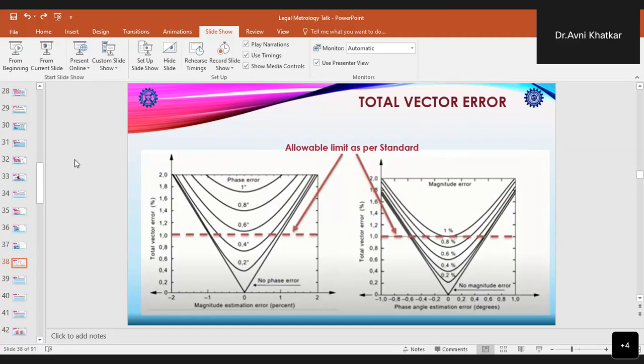In the first figure, we have the magnitude error estimation. If we have no phase error, then we can see from this graph how the total vector error changes as the magnitude error increases. Similarly, in the second figure, there is no magnitude error at the zero point, and then it increases. The allowable limit as per the standard is 1%, so total vector error can be maximum up to 1%.